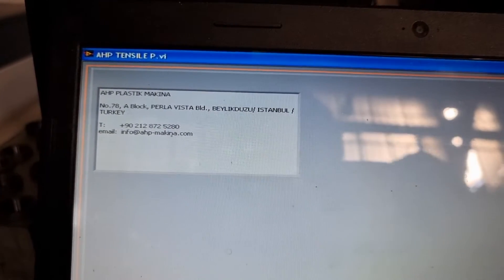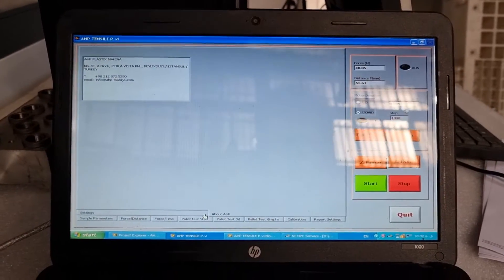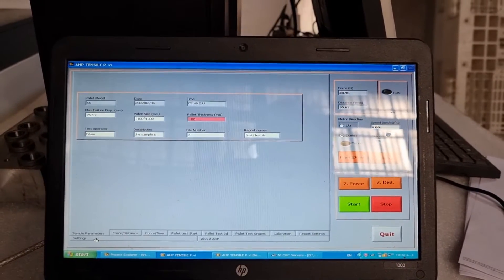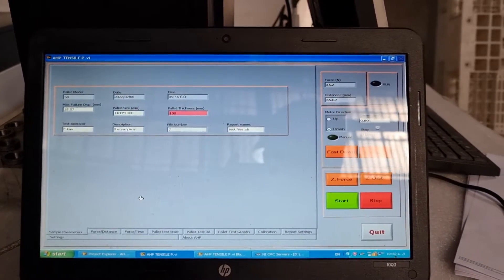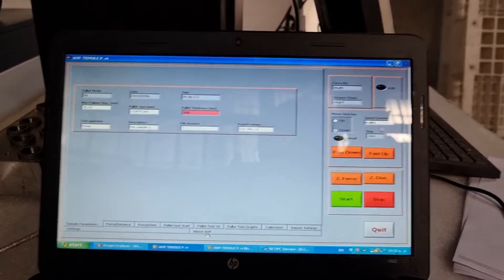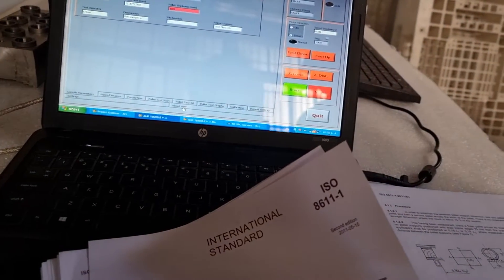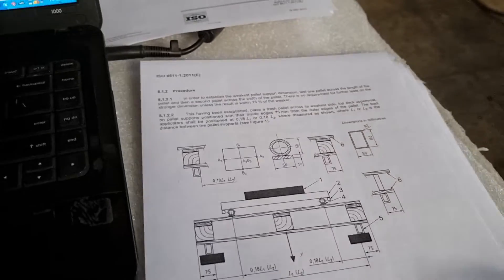Hello friends. I'm going to show you how to do the pallet strength test using the AHP pallet testing machine. This is a 15-ton force capacity pallet compression tester unit from AHP Plastic Makina. The machine works according to ISO 8611 standard, and now I'm going to do the test of strength.